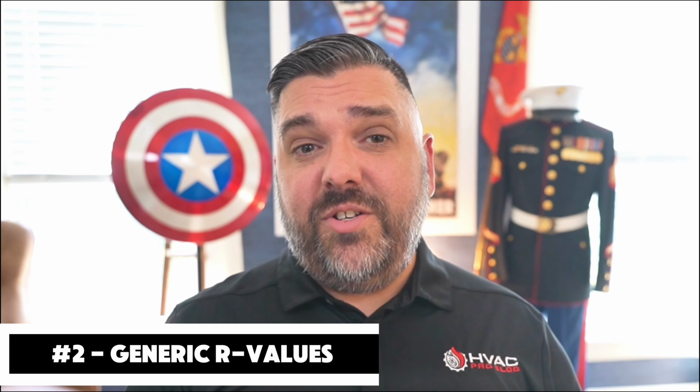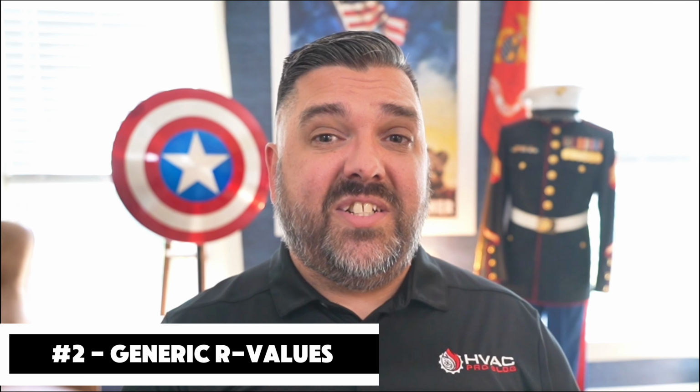All right, mistake number 2 is even more common, and it's costing contractors thousands in callbacks. They're using generic R values instead of measuring actual insulation. I was called in to troubleshoot a system where the contractor had calculated the load based on R19 wall insulation. Sounds reasonable, right? The problem was this. That 1985 house had maybe R11 insulation that had settled and compressed over 30 years. The actual thermal performance was closer to R8.